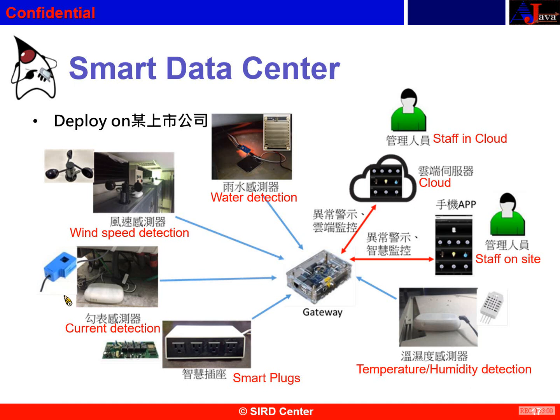When there is no power from the city, they automatically turn on the diesel power generator. But we detected 2 times that although the diesel power generator was turned on, the power did not go through to the data centers. Then we sounded the alarm immediately, and they fixed the problem.